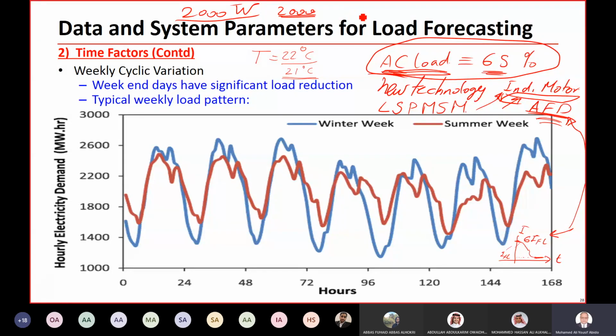As we mentioned earlier, back-to-back conversion: you have AC to DC, and this is 60 hertz. You rectify the 3-phase AC here, and you have a very small DC link, and then DC to AC. You invert DC again to 3-phase AC, but not at 60 hertz. You can have 30 hertz, or 35 hertz. You can control it gradually, so you can control the speed of the motor gradually. So this will reduce, of course, the full load current.